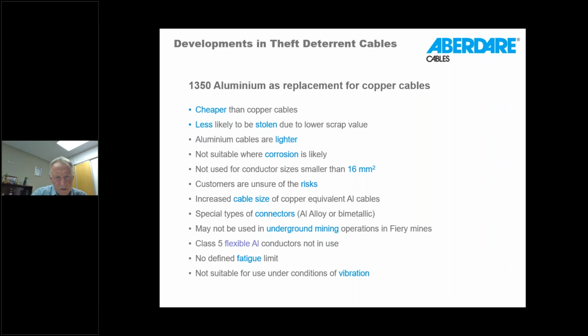Class 5 flexible aluminium conductors are not generally in use, although we have made such cables and are supplying to one of our mining customers for surface mining operations, and it's worked very well. And surprisingly, these aluminium flexible conductors have quite a high fatigue limit, so we've not really seen any significant issues with using these types of flexible aluminium cables for trailing cable applications. In our case, it was up to 33 kV. There's no defined fatigue limit for aluminium in general, so the fatigue performance is quite good generally, particularly if you're using annealed aluminium.